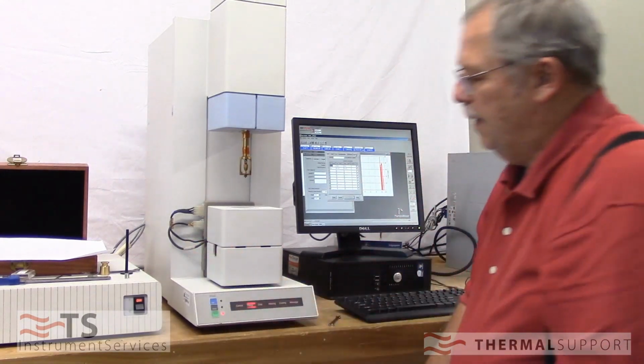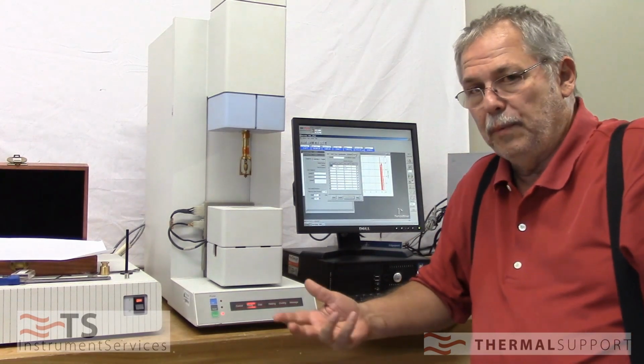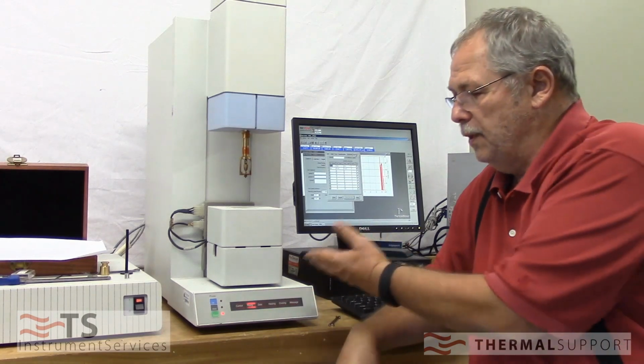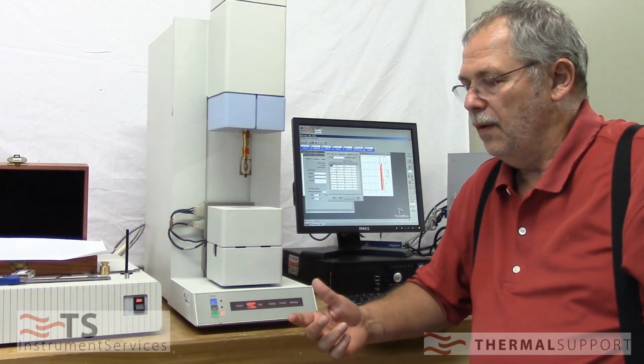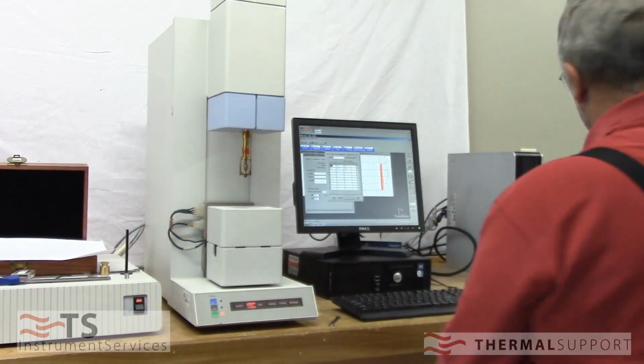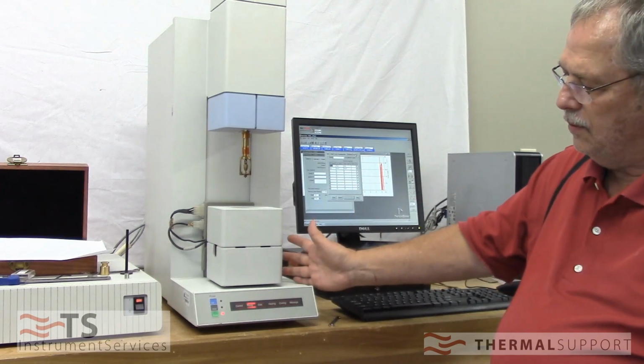You're going to want to do those with whatever sort of coolant that you have on this analyzer. You notice right now we do not have a coolant. However, when we worked on this analyzer, we had a recirculator there with what they call a turbulent chamber put on this. So there is a turbulent chamber accessory that comes onto this analyzer that you can run a liquid to. There also is an Intracooler 1, Intracooler 2. Those are small mechanical chillers that will allow you to go to minus 35 degrees C and minus 65 degrees C.